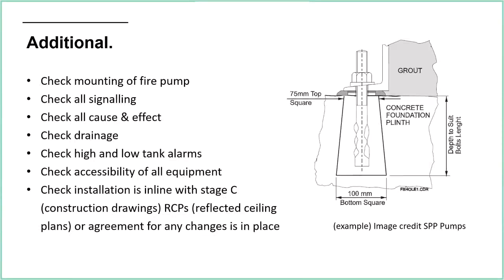Check drainage. Drainage is a common problem. Just undersized drainage can be a real issue. So often that's specified well in advance, but then when it comes down to it, it's a case of, well, hang about, how come there's only a standard 25 or 32 mil drain here? We need a much bigger drain for our sprinkler pipe work, because we've got to allow for various things to happen at the same time. The tank may be overflowing, opening the drain valves on the alarm valves. Often all this equipment is in the basement, and so drainage can be problematic. So that just needs checking through.